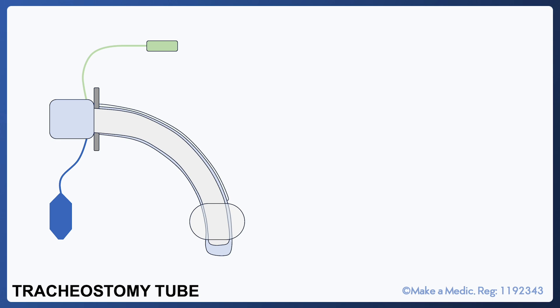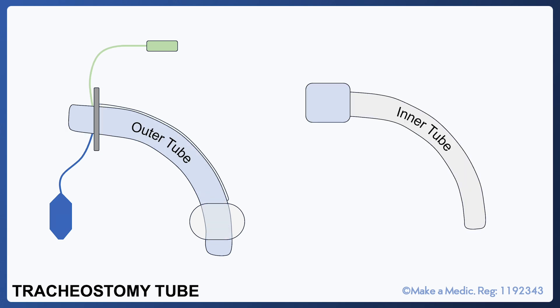One very important point to know about tracheostomy tubes is that they are actually made up of two tubes: an inner and an outer tube. The inner tube can be easily removed whilst keeping the outer tube in place. It's designed this way so that if mucus were to obstruct the lumen, the inner tube can be removed and replaced. Note that the outer tube may have a different external component to the inner tube and may not connect directly to the ventilator without some sort of adapter.